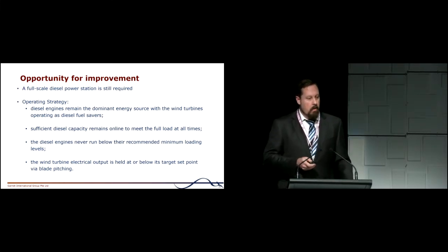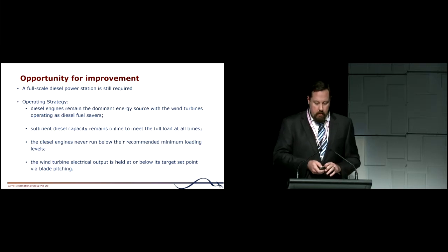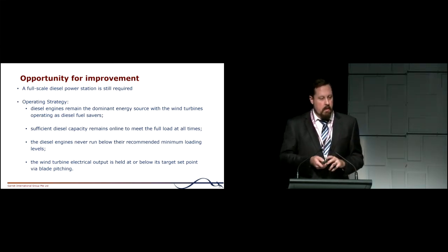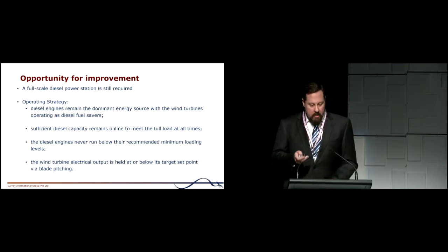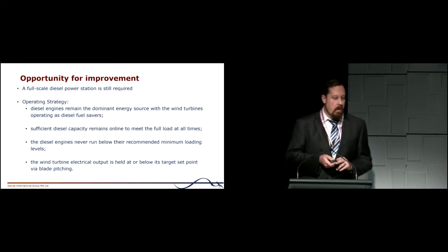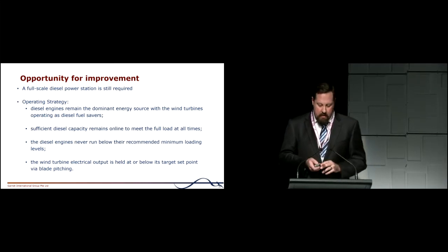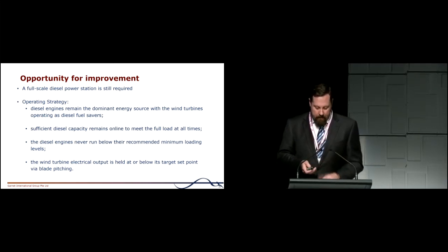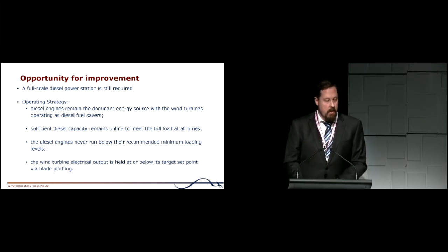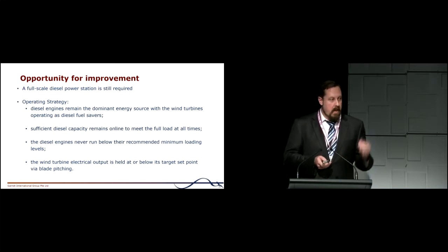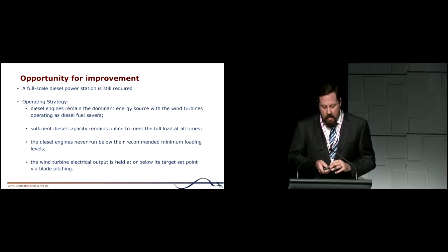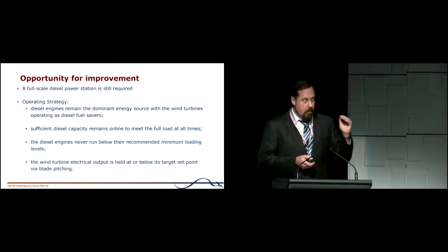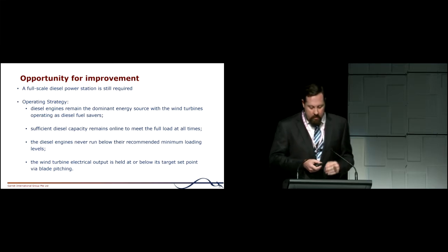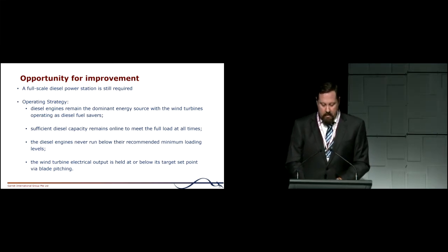The operating strategy used in the model was to use the diesels as the dominant source of energy, offsetting that diesel consumption with wind. Sufficient diesel-generated electrical capacity must always be online to meet full demand, and this is where we see some inefficiencies creeping in. The greatest inefficiency arises from diesel generators running underloaded, a bit inefficiently. As a result of diesel being the dominant source, the wind turbine's electrical output is held at or below its target set points by blade pitching, responding to system frequency and voltage movements, to make sure the diesels are always in control.